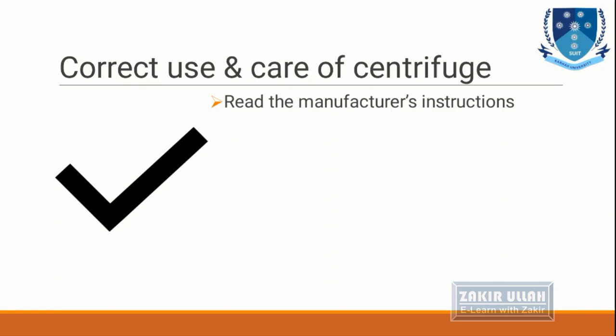Place the centrifuge on a hard, level bench out of direct sunlight, towards the back of the bench. Usually we try to avoid direct sunlight on any instrument. So the centrifuge is also placed in such an area where no direct sunlight is in contact with it, and it is placed near the wall at the back of the bench.